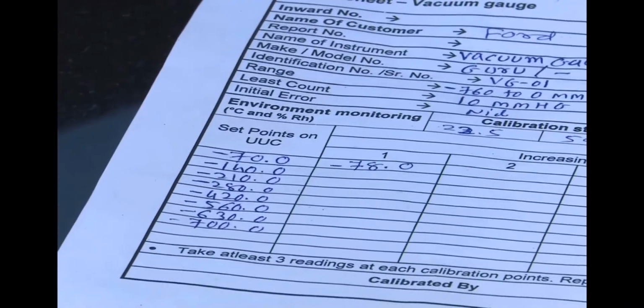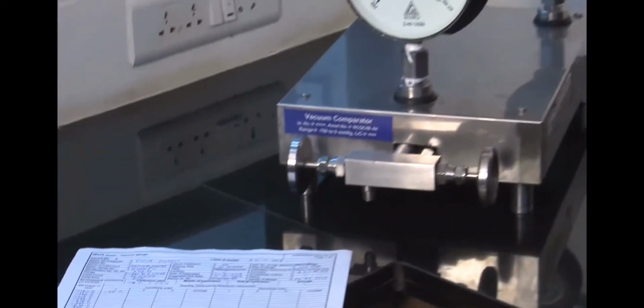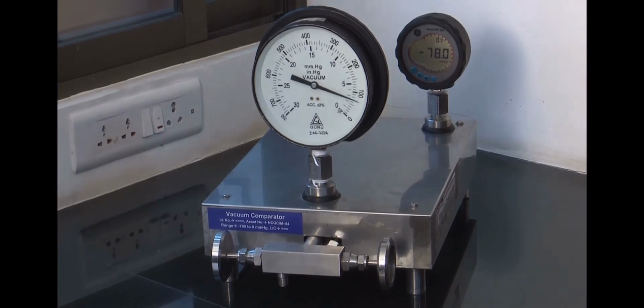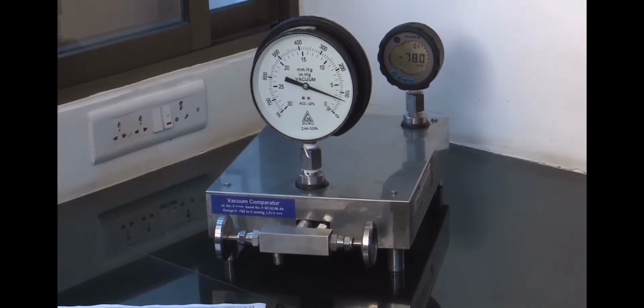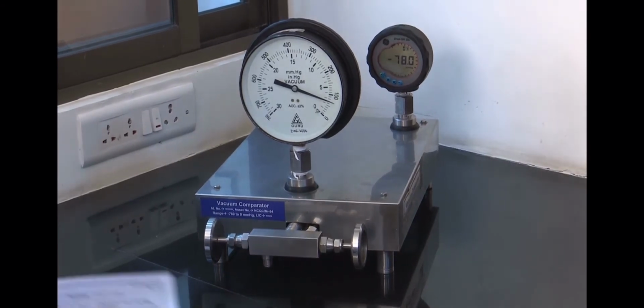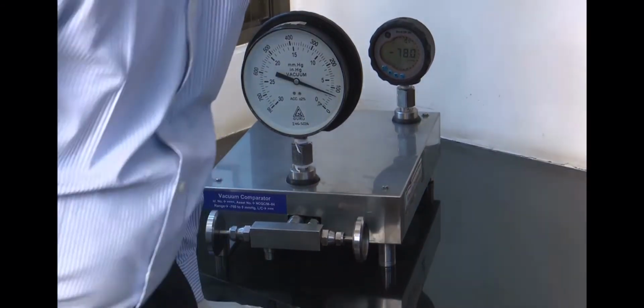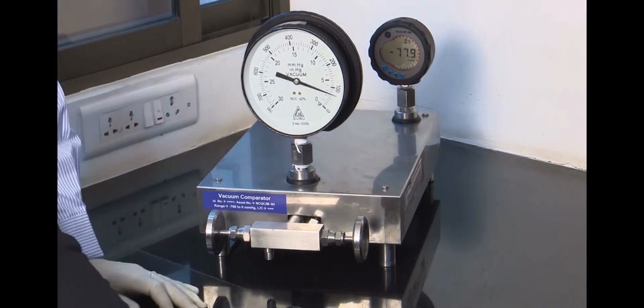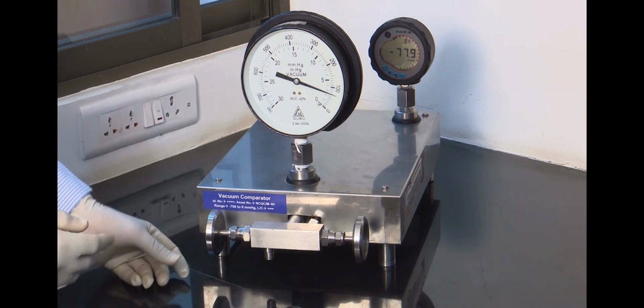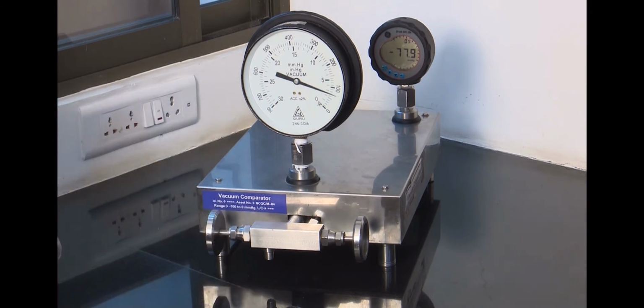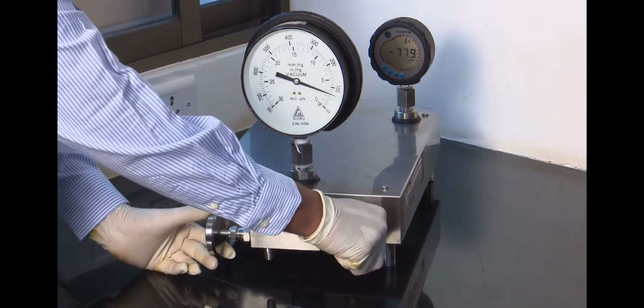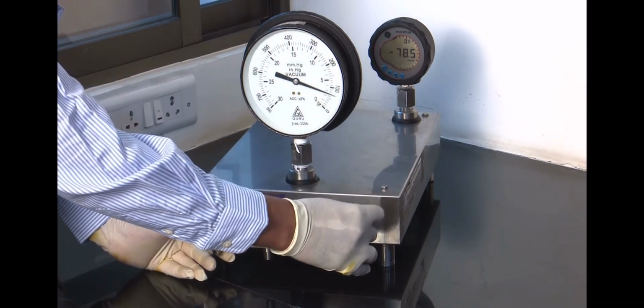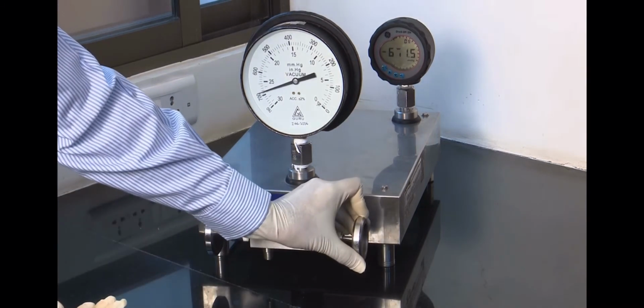Same way, we can do calibration for all the calibration points as per the DKD R61 and record the readings in worksheet. Now I am demonstrating calibration at the last calibration point for increasing cycle at minus 700 mm Hg. Now start calibration for decreasing cycle.